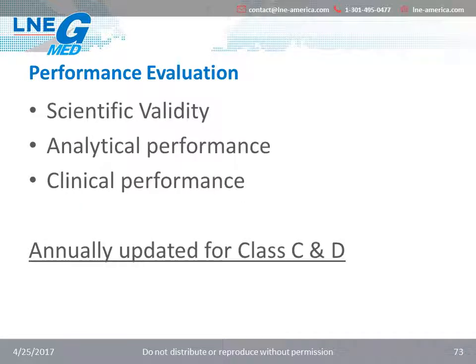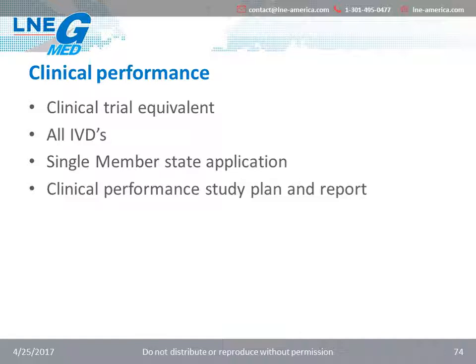The performance evaluations are based on the assessment and analysis of data to establish or verify the scientific validity, analytical performance, and clinical performance. Per the new regulation, manufacturers must develop a plan and procedures to continuously perform and document performance evaluations, with prescriptive frequency required for IVD devices that are high-risk classes. Performance studies are the equivalent of clinical trials in the new regulation.